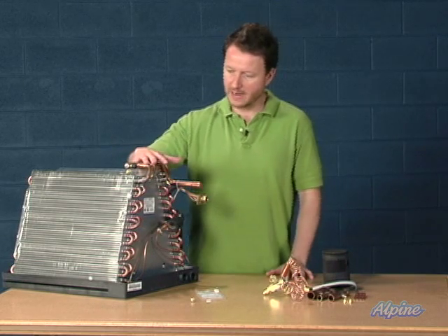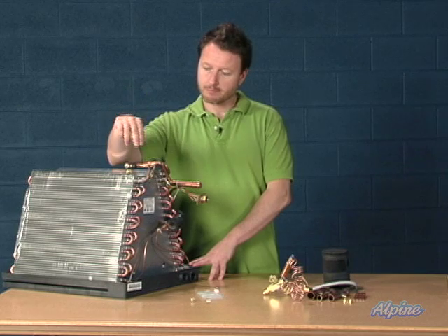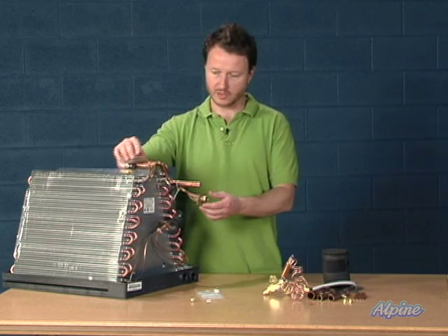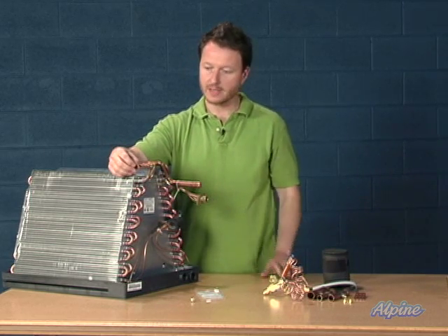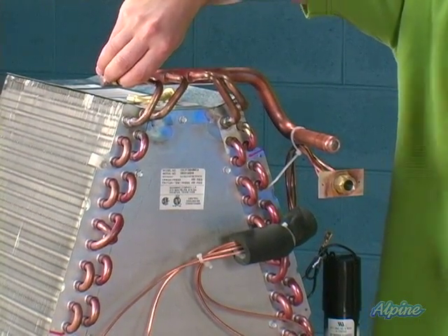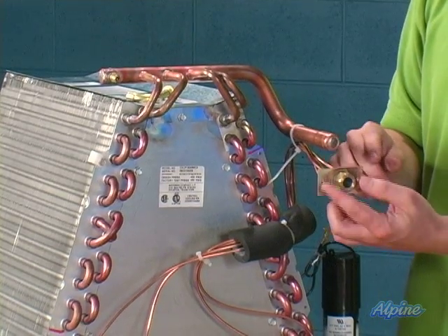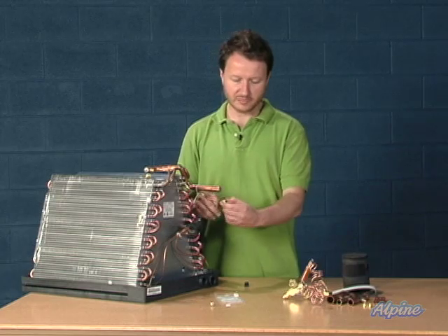So here we go. This is an evaporator coil. When it's brand new, it's going to come pre-charged with nitrogen. It's an inert gas, so the first thing you want to do is release that, either at this fitting here or over here. I've done that in advance already. Simply take this off, and there's a little Schrader valve in there. Push it in with a screwdriver or something like that. You'll hear a hissing noise. Let that out. Alternatively, you can loosen this with a wrench. Let that occur for a couple of minutes until the hissing stops, and then you can safely take this nut off.